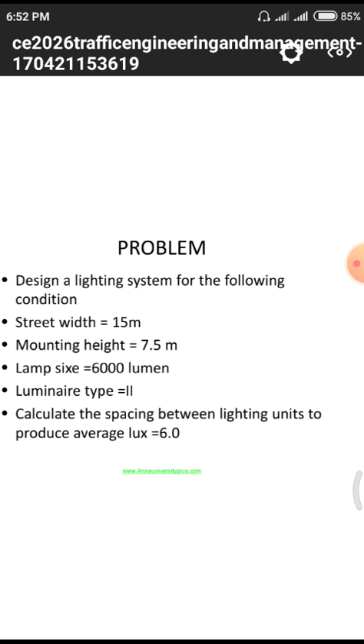This is the design example problem. Normally, what are the terms associated with these lighting parameters? First of all, we have the total street width of 15 meters and mounting height. Normally we go for a 6 meters height, but here we have a height of 7.5 meters and the size of the lamp is 6000 lumens. Illumination type is type 2. Calculate the spacing between the light units, projecting average LUX equal to 6.